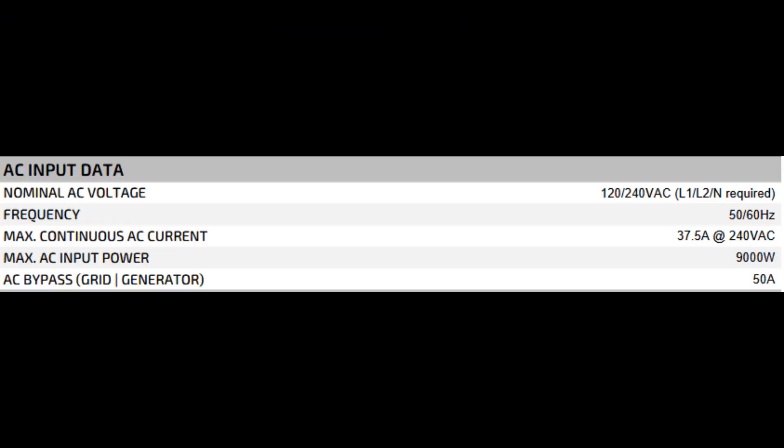The spec sheet says nominal AC voltage 120 to 240 volts AC, L1, L2, and neutral required. Frequency 50-60 hertz. Max continuous AC current 37.5 amps at 240 volts AC. Max AC input power 9,000 watts. AC bypass grid, generator, 50 amps.